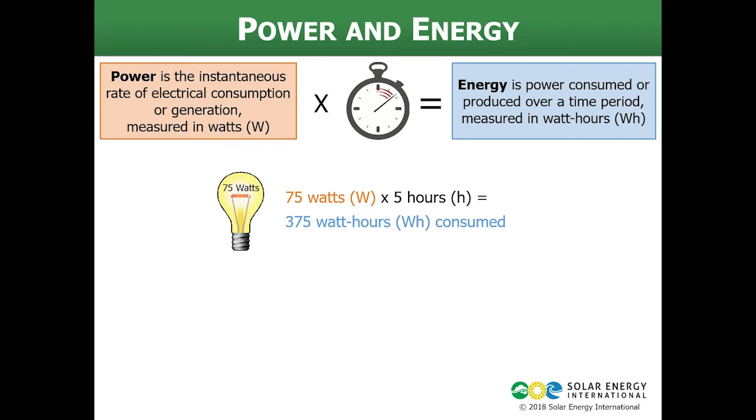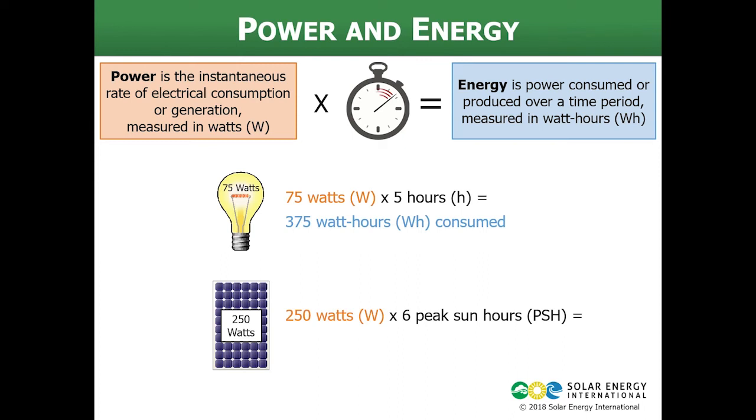Now if we flip that into production, since we're talking about PV systems, if we have a 250 watt module, so that's the power rating of the module, 250 watts, and we have six peak sun hours, over those six hours this 250 watt module will generate 1,500 watt-hours or 1.5 kilowatt-hours.